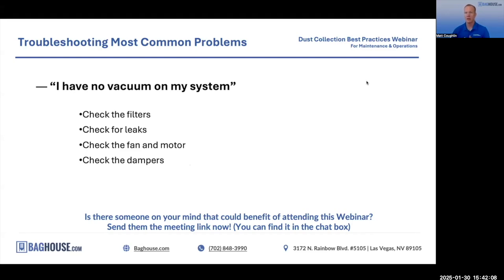So we'll look at the fan itself just from a basic maintenance and PM perspective and say, how does the fan wheel look? What's the fan RPM? We can stick a probe just upstream and figure out what the actual airflow and the vacuum pressure of that fan is, and make sure that it matches up to what it should be for your system. And then finally, some systems will have dampers, slide gates, and other manual methods of airflow control, which can greatly modify the balance of your system.